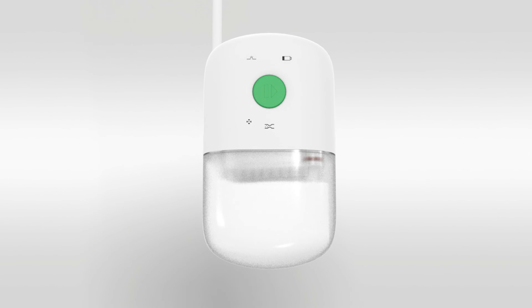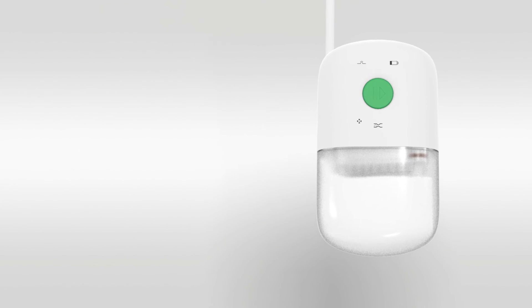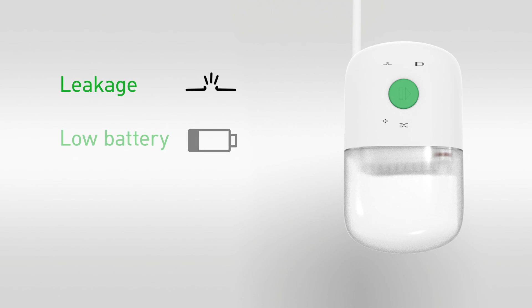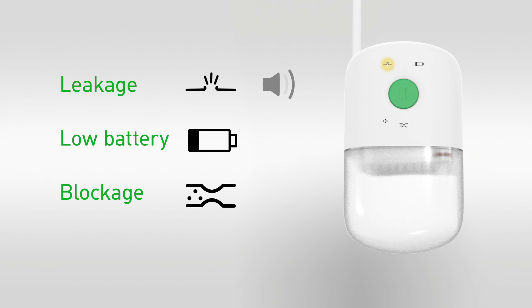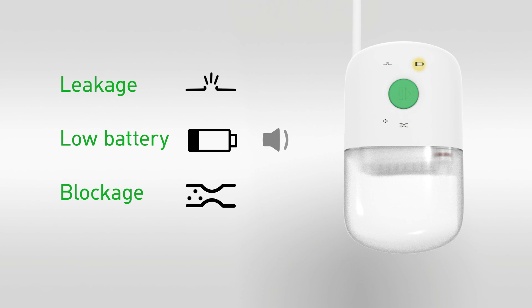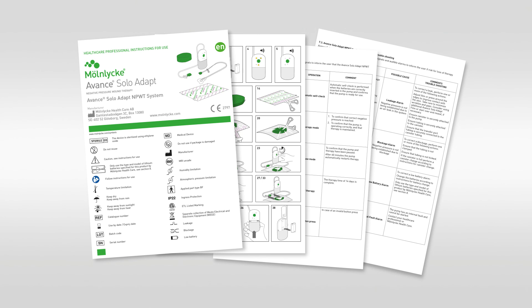Finally, to ensure the delivery of safe, effective negative pressure therapy, the Avance Solo Adapt pump has three audiovisual alarms for leakage, low battery and blockage conditions. If you experience a blockage or leak alarm event, the system will issue an audible alarm and the associated alarm symbol will illuminate. The pump will go into a paused state. The device continues to run while a low battery alarm is active. For further information, please refer to the printed instructions provided with your Avance Solo Adapt negative pressure wound therapy system.